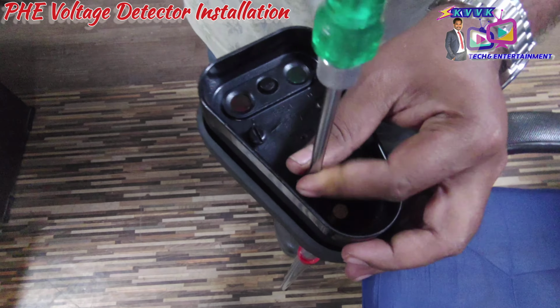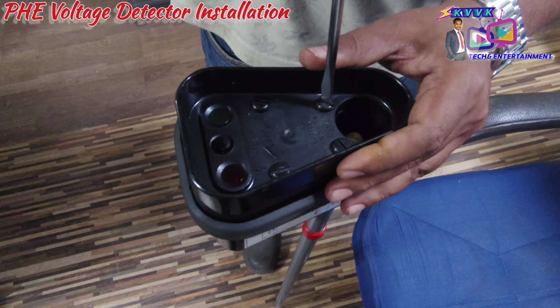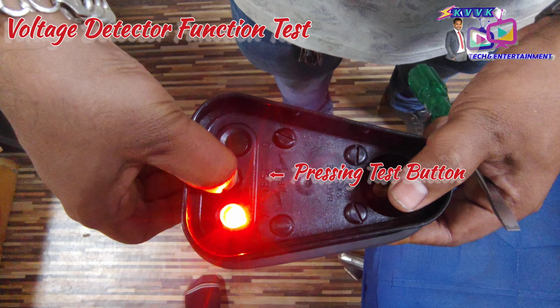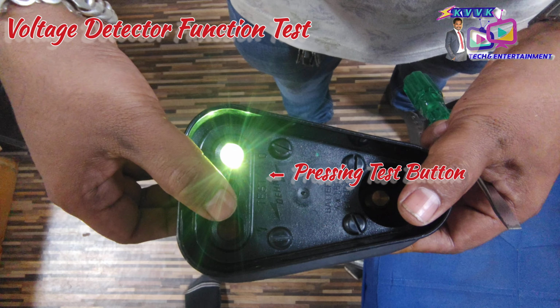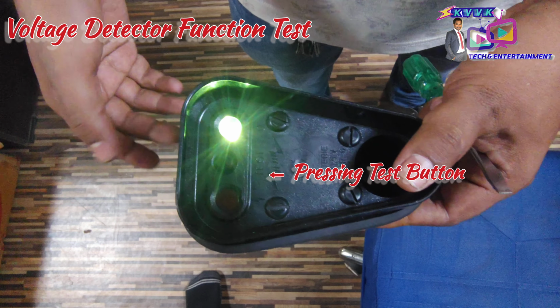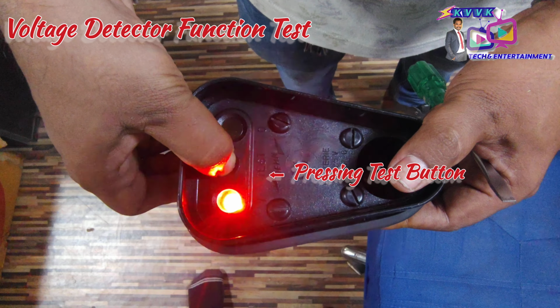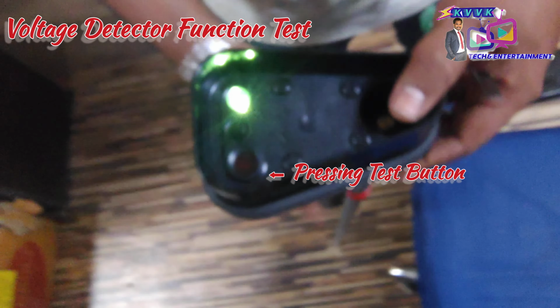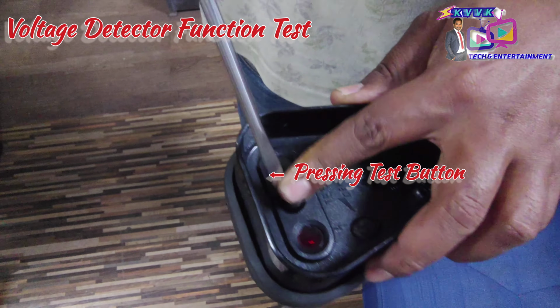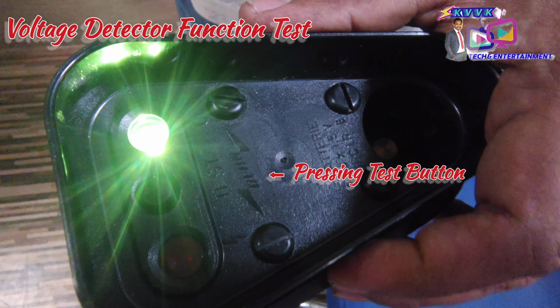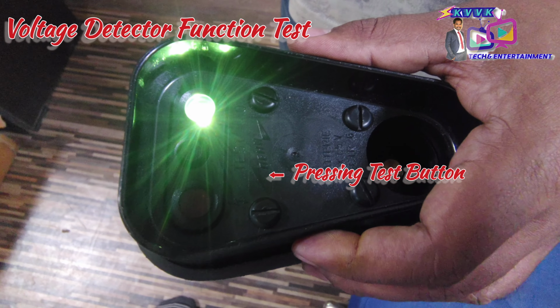Now we will go for the function test of the voltage detector. The function test must be carried out before testing for safe isolation. By pressing the test button, the red lamp lights on. Pressing the test button, the acoustic indicator gives an intermittent signal, and the green lamp is on when the test button is released. The voltage detector is now ready for operation for about 40 to 60 seconds.